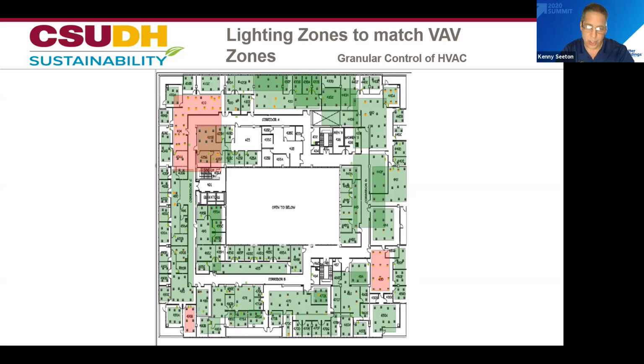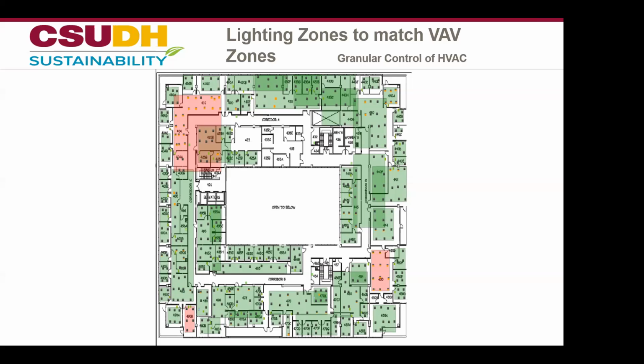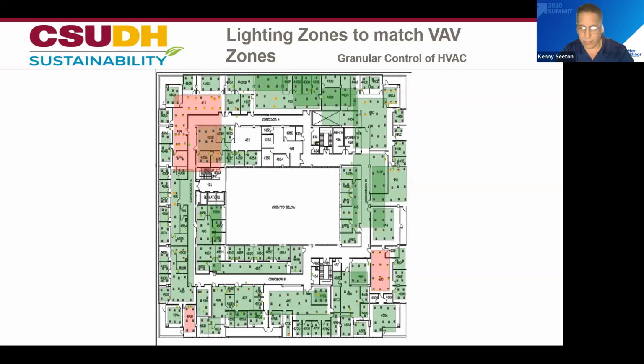So when we control that space on the HVAC, we're pretty much setting a schedule from 7 in the morning until 10 at night. Now, with the lighting controls, we know if somebody's in the space or not, and we can group that into one control point that says, hey, all the lights in these 4 offices are off, nobody's in there, turn off the VAV. But then we have to figure out how to bring that into the building automation system.